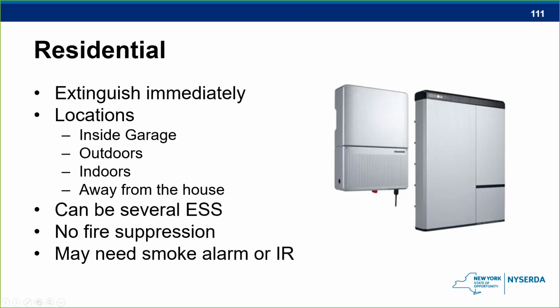There could be several of them. It could be up to 4 of these particular cabinets on the outside, so it may be more than just one of them in there. They do not have any fire suppression in a private dwelling. They will not have them in the residential ones. And they may have a smoke alarm or an IR detector, infrared. So in garages, for instance, smoke alarms may not be used. They may use an infrared detector to look for flames. So all of that should be included if you're putting them inside the building itself.